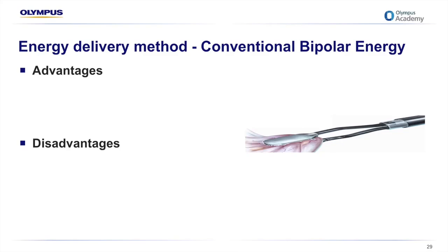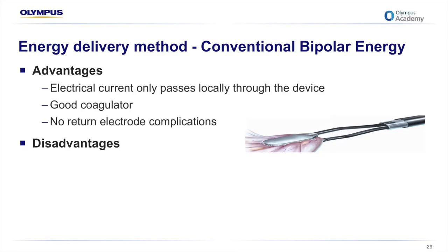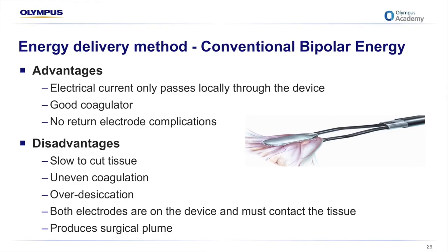Bipolar energy is different than monopolar energy. With bipolar, the tissue effect takes place between two electrodes of the device. Electric current passes directly from one electrode through the tissue to the opposing electrode and then back to the generator. Current doesn't pass through the patient's body, only through the tissue between the electrodes. If both electrodes are not in contact with the tissue, the device will not function properly. Conventional bipolar devices are good coagulators, however, they can be very slow or possibly not cut the tissue effectively. Once again, surgical plume is created here.